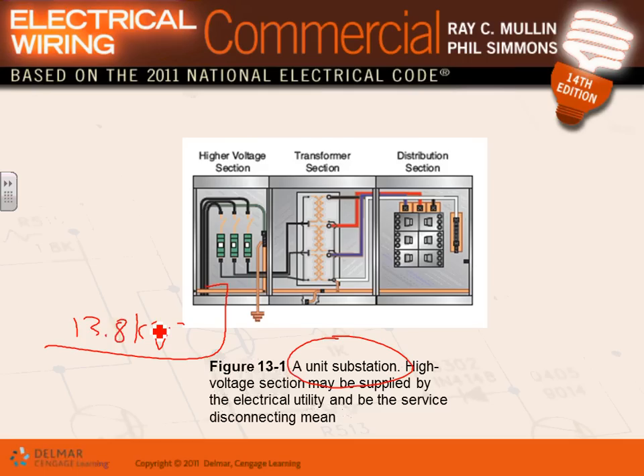And we will be touring places where they have this in the spring. So they're bussed together internally. Here's your transformer, and it's bussed internally into another panel. Typically they use this application in hospitals and sport arenas, a nice cut, all in one. So you have your 13.8 kV, your 1.5 MVA transformer, and your voltage, which is 480 slash 277 or 208/120, all bussed together. This is an expensive deal. And then the utilities can do their metering inside on the high voltage side or the low voltage side.